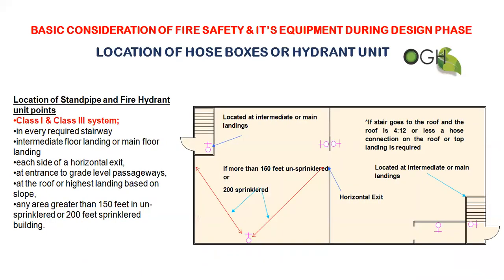Now, we have to set it in every required stairway. The placement locations include: intermediate floor landing or main floor landing, each side of the horizontal exit and entrance to the grade level passageways, and at the roof or the highest landing based on the slope.